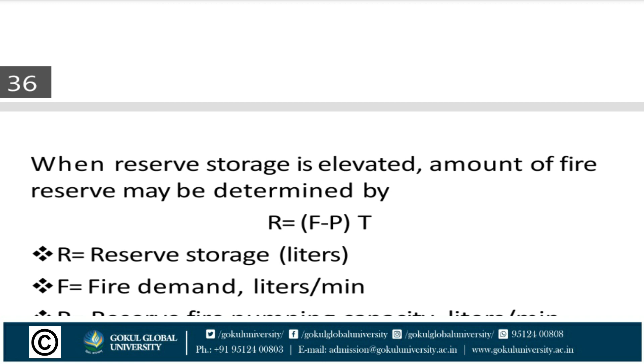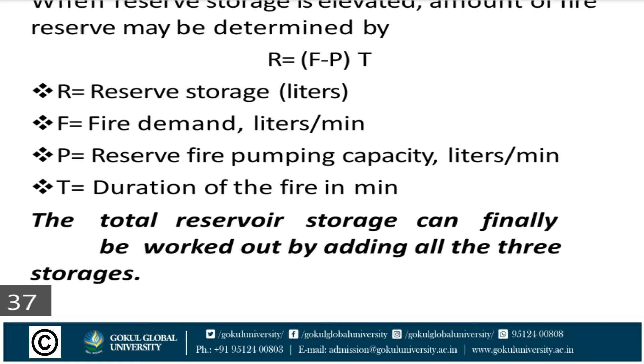When reserve storage is elevated, the amount of fire reserve may be determined by R = (F - P) x T, where R is the reservoir storage in liters, F is the fire demand in liters per minute, P is the reserve fire pumping capacity in liters per minute, and T is the duration of fire in minutes. The total reservoir storage can be worked out by adding all the three storages, which gives the total storage of ESR.